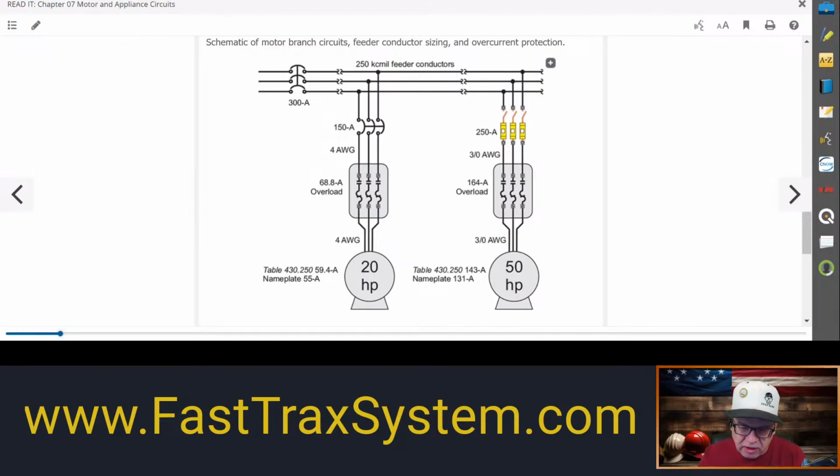So somebody comes and changes this motor, and maybe it's even a more efficient motor as time goes on. If we traditionally size everything based on the FLC, then we know we're going to be okay, and the conductors are going to be sized more conservatively than they possibly would be for the FLA, which is on a nameplate and can change for the motor. Why? Because it has to do with power factors, and all kinds of things can affect the FLA, but the FLC is constant. So if we're sizing things on that constant, it's going to be pretty consistent.